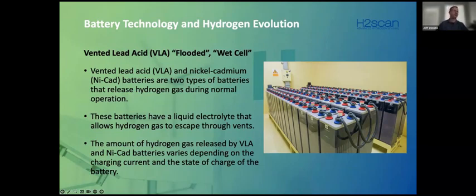There are some safety mechanisms on the battery. As you can see, these caps on the top are called flame arresters, and they're used in two different ways. They disperse hydrogen from the top of the battery, but they also prevent flame from entering the battery, because you always have hydrogen between the water level and the jar cover of the battery. These basically vent hydrogen normally during normal operation, and of course during boost or equalized charge they increase the amount of hydrogen. Anytime you're recharging, it increases the amount of hydrogen output.